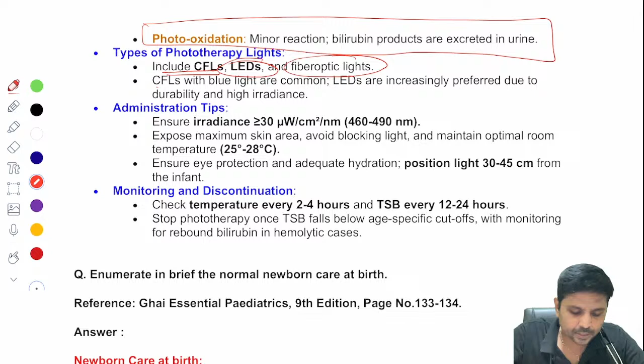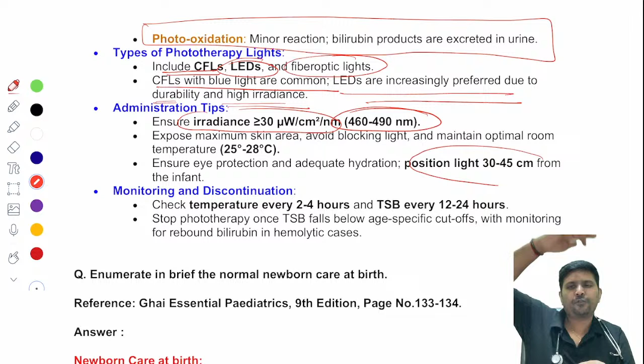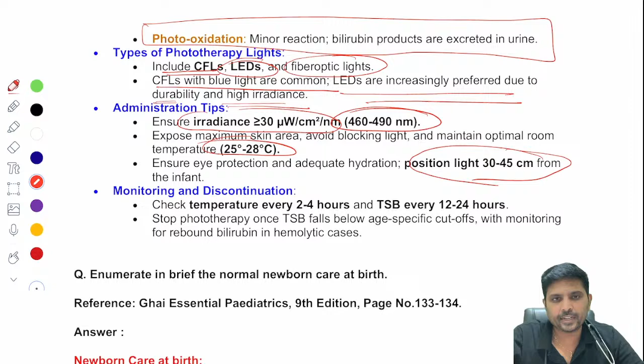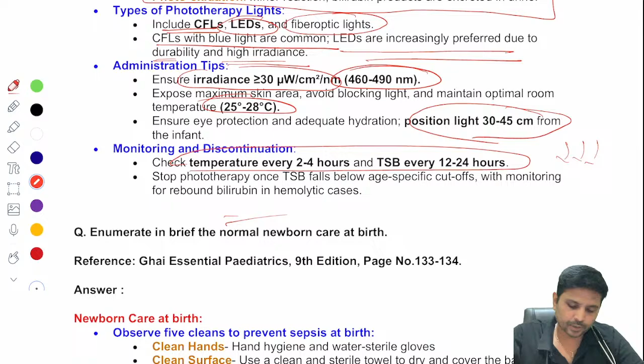So what is the minimum phototherapy dosage that should be used? Ideal wavelength is 480 plus or minus 10 nanometer. Ideal irradiance is more than 30 microwatts per square centimeter per nanometer. Usual distance between the phototherapy and the child will be 40 centimeter. Very important, 40 centimeter. Optimal room temperature, as for delivery, is 25 degrees Celsius. Remember, you need to check the temperature every 2 to 4 hours because it can produce hyperthermia. Usually with phototherapy, the serum bilirubin gradually falls.